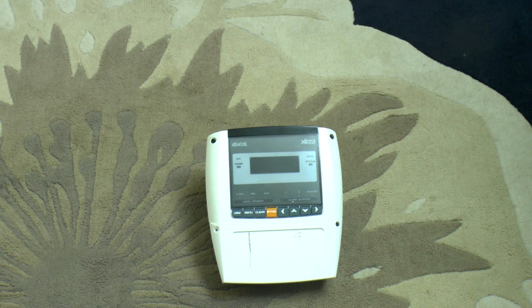As a result, the first half of the update went okay, but when I went to do the second half, the updater froze at the 0% mark. After a minute or so, I power cycled the control to have another go. Unfortunately, one of the first things the XWEB had done was wipe its built-in web server. Once it booted, it just displayed an "error loading, reboot system" message, and trying to web browse to it just resulted in a 404 error, page not found.